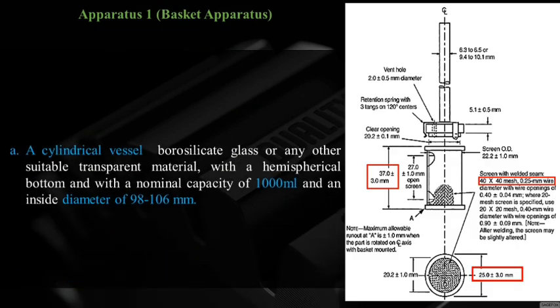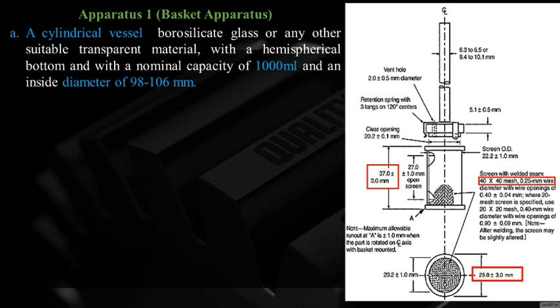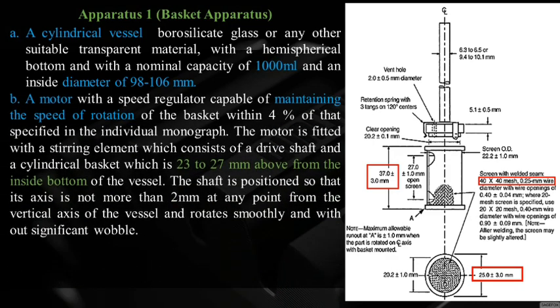Apparatus 1 — Basket Apparatus (USP): consists of a cylindrical vessel made of borosilicate glass or suitable transparent material with a semi-spherical bottom, capacity of 1000 mL, and internal diameter of 98 to 106 mm. A motor with a speed regulator maintains the rotation speed of the basket within 4% of the specified value. The motor is fitted with a drive shaft and a cylindrical basket positioned 23 to 27 mm above the inside bottom of the vessel.